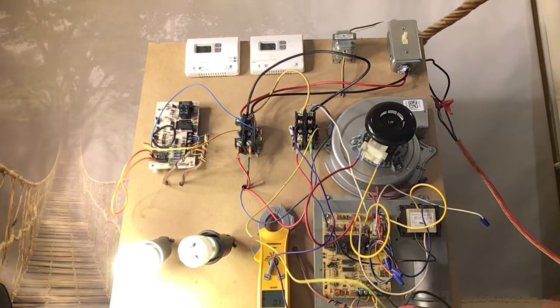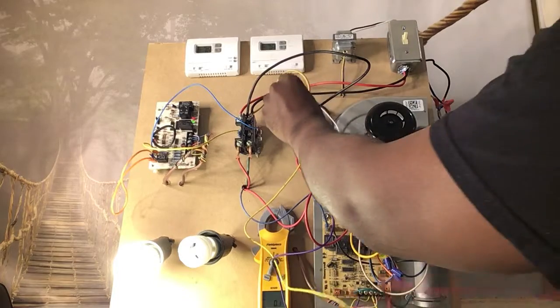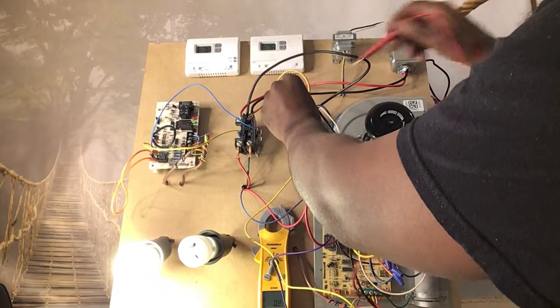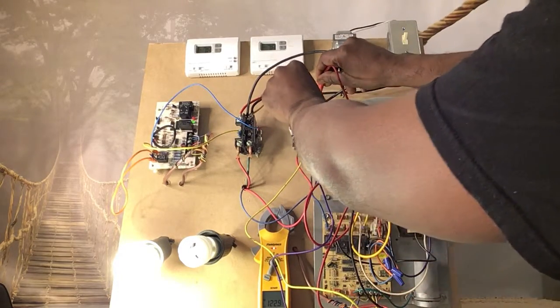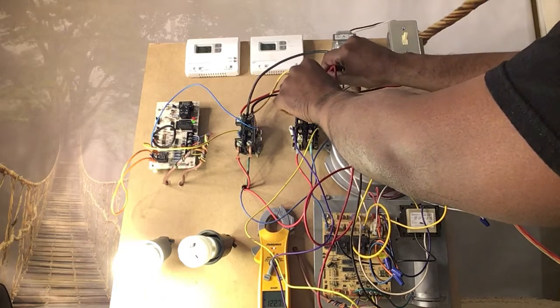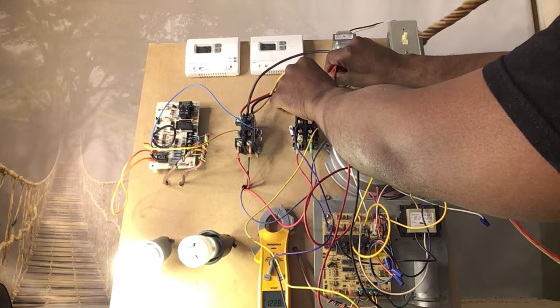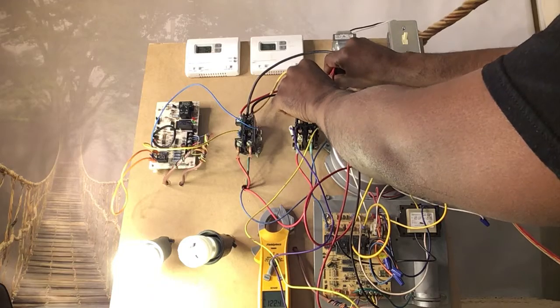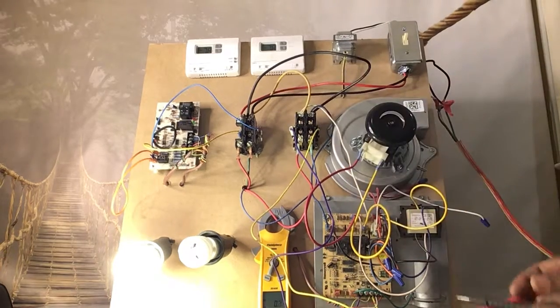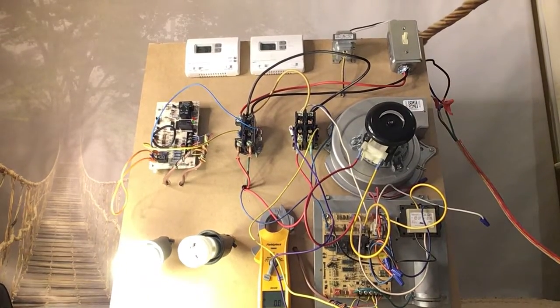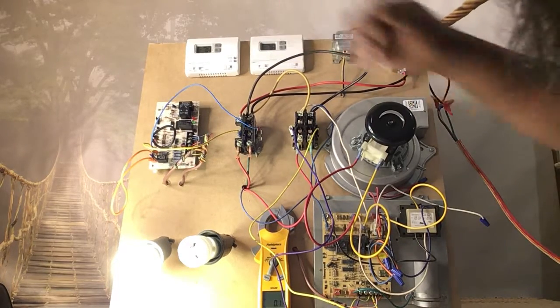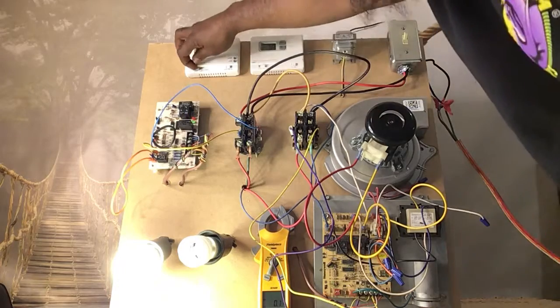So now this should be reading 120 volts, and it looked like one of the stats was already on because there's a contact in. But if you can see that, that's 120 volts. That is on alternating current, and we pretty much now just ran through a complete cycle on the heat pump's side. Let's see if I can shut that off.